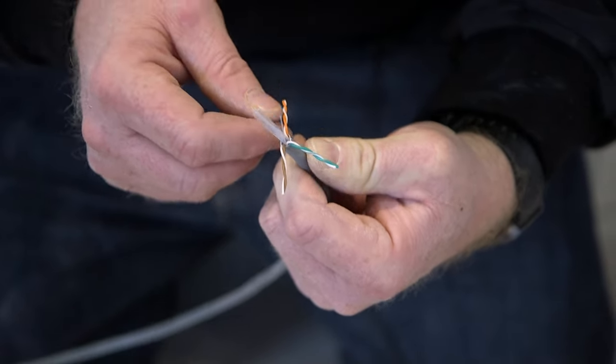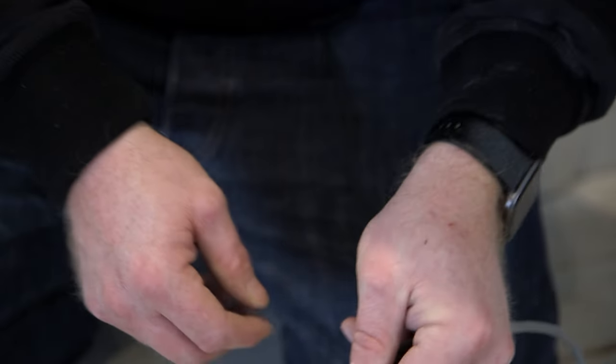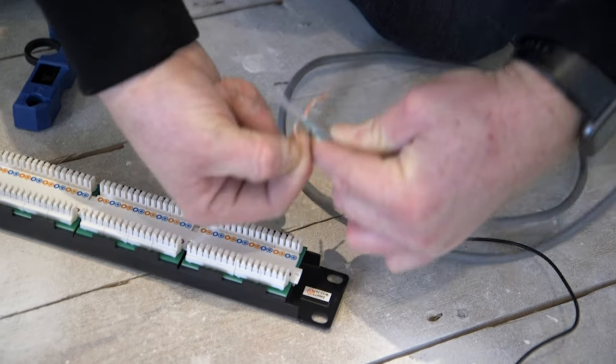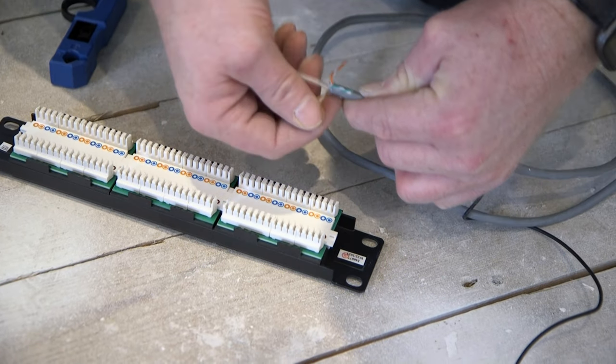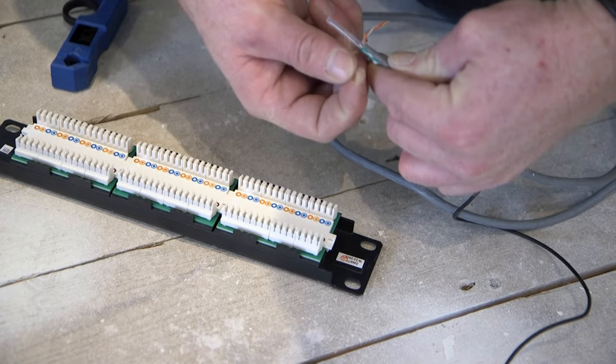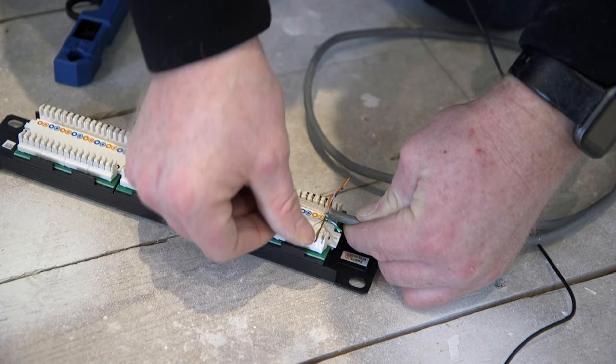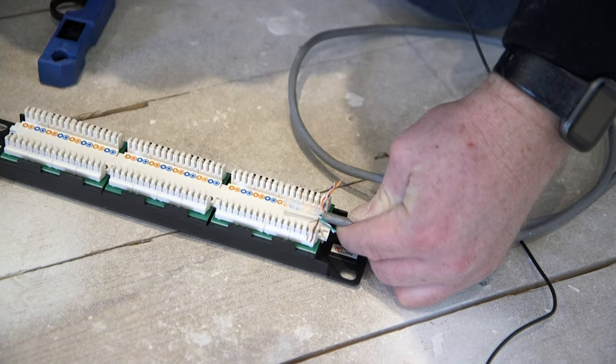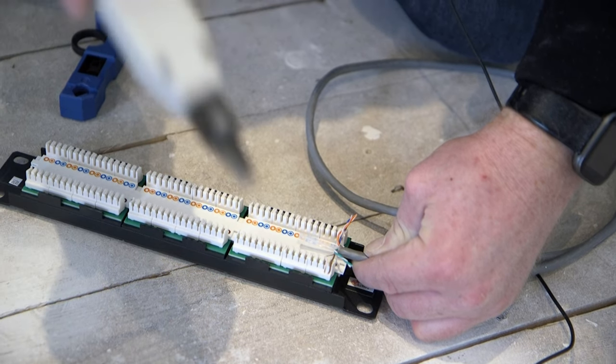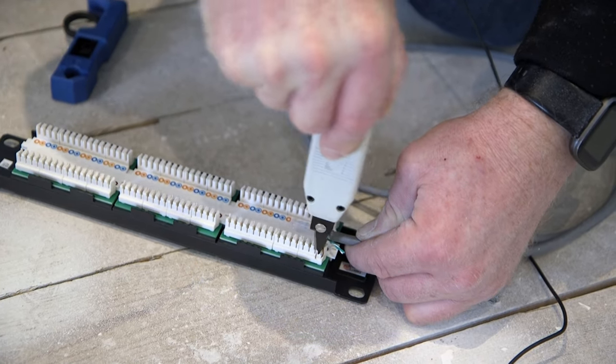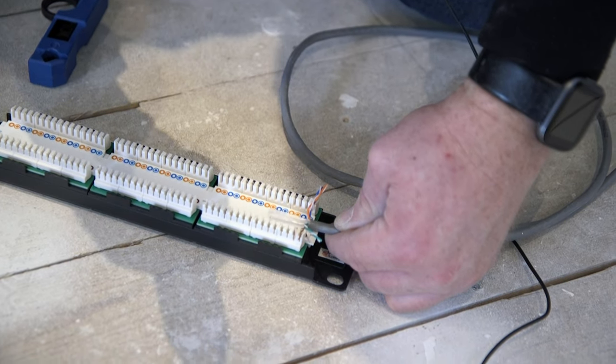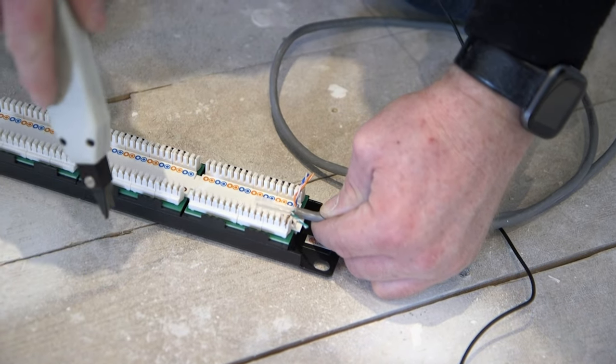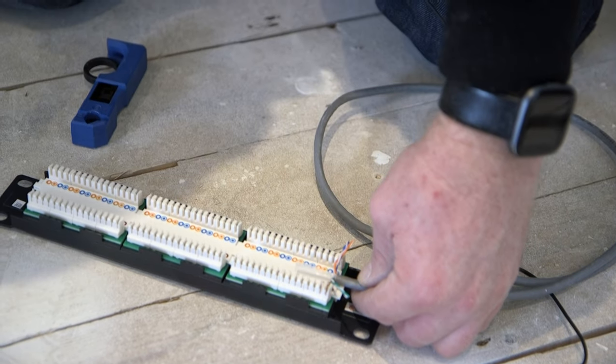You can see inside the ethernet cable we've got four twisted pairs, eight cables in total. From here what we then do is marry these pairs up to the individual cable connections here. So we've got brown, brown and white, and then we use a punch down tool. This one's got a cut on it as well. From there we can literally punch down and cut the cables. It's as simple as pressing this down to lock them in and they're done.